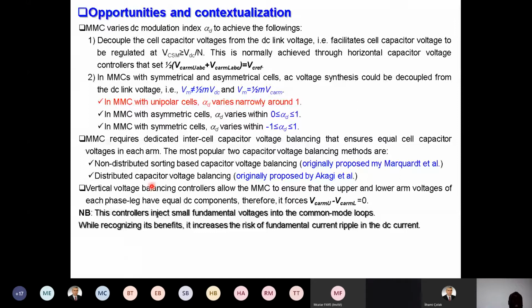These are the two, and I'll explain this one later, and the merits of each approach. And also we will need vertical capacitor voltage balancing, which allows the MMC to ensure the upper and lower arm must have equal DC voltage. And this is important, especially in real applications, because of the tolerances of the capacitance and inductance of real components. You have to have this controller to ensure the upper arm has the same voltage as the lower arm to prevent appearance of the DC component in the output AC voltage.